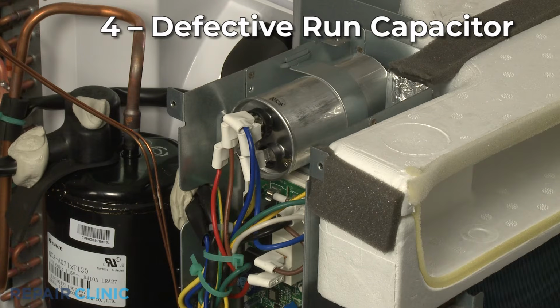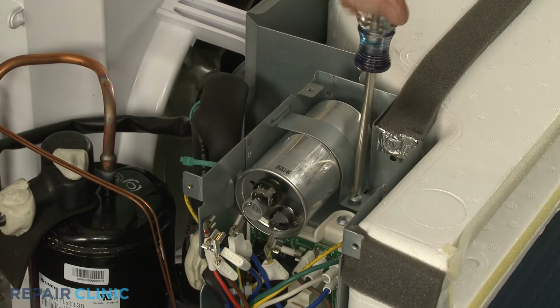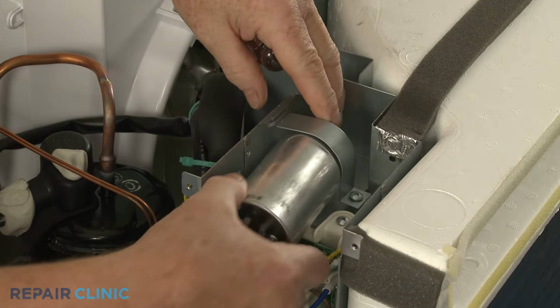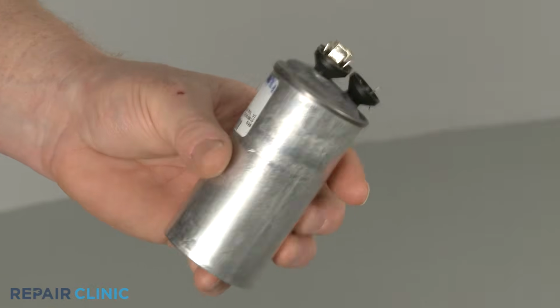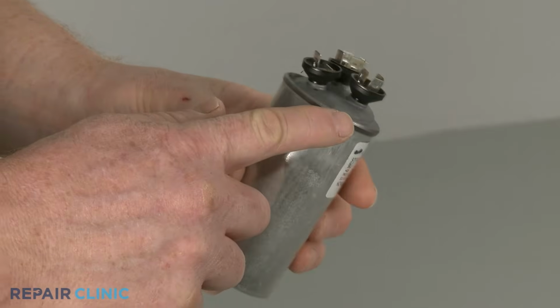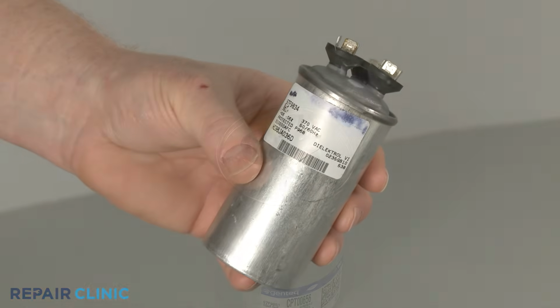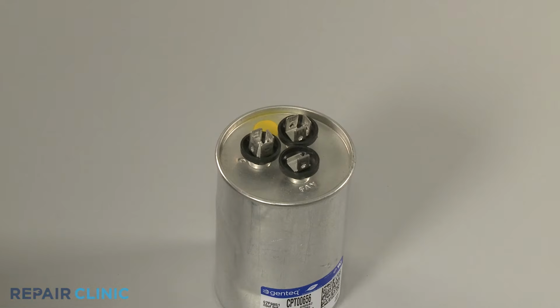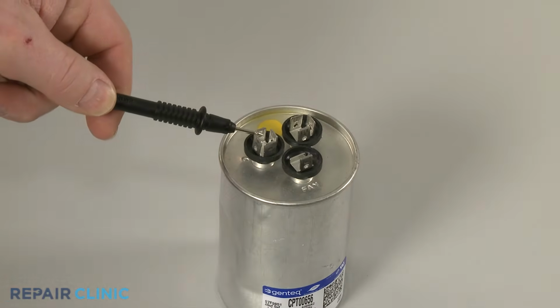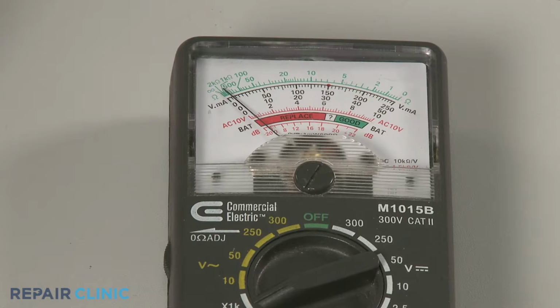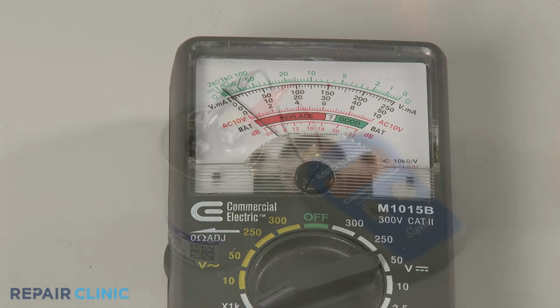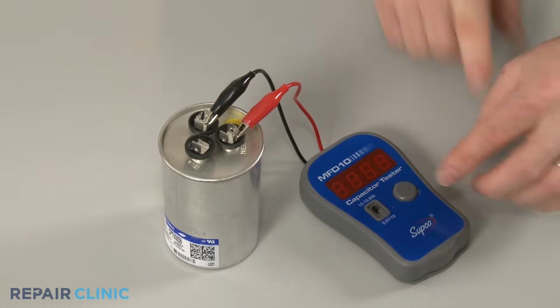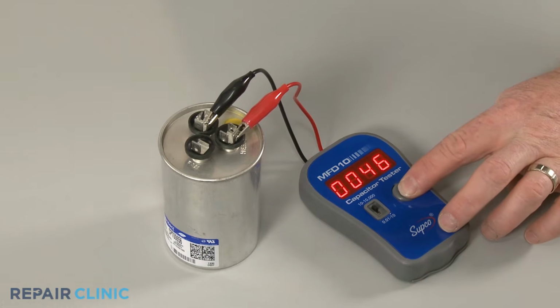A run capacitor stores an electrical charge, then releases it to power the compressor or fan motor. If the capacitor is defective, the air conditioner may be unable to cool. When a capacitor fails, it will often bulge or leak. You can also determine if a capacitor is faulty by using a multimeter to test the capacitor's ability to store and release an electrical charge, as well as determine if the component has a proper capacitance rating, provided the multimeter has a capacitor testing function.